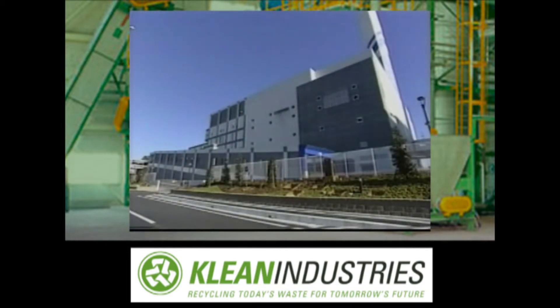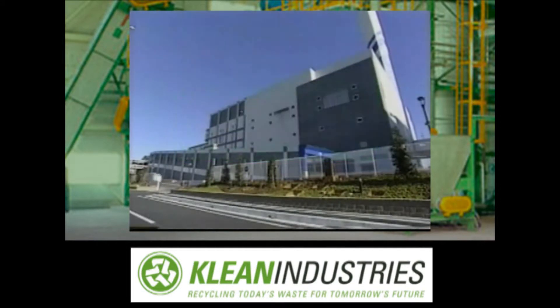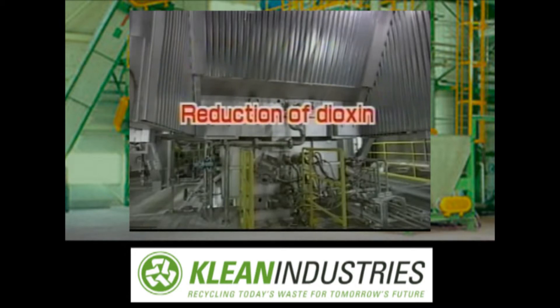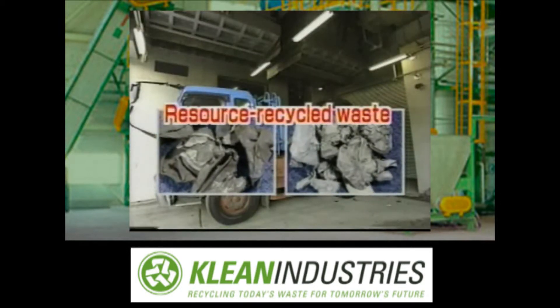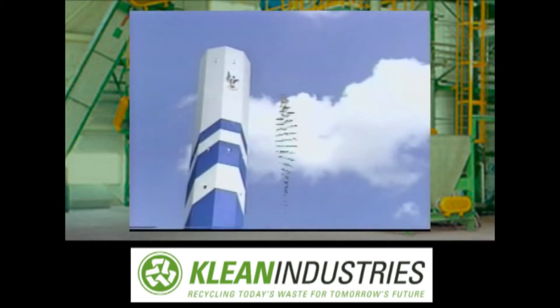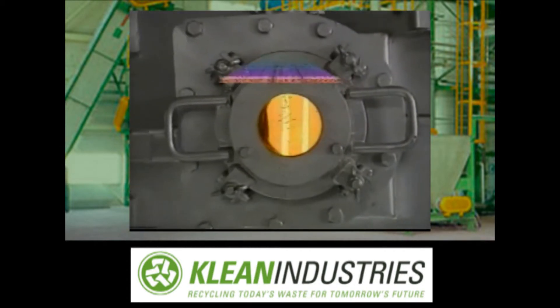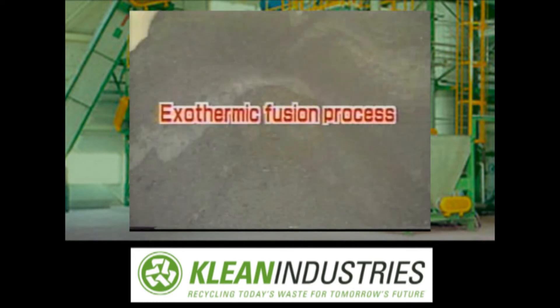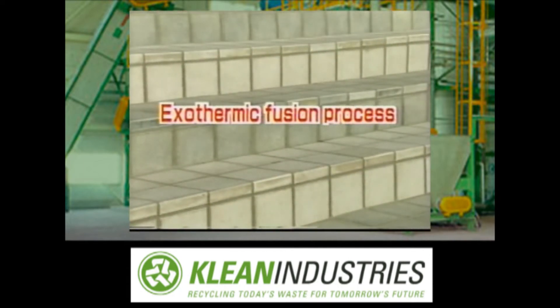Let's review the major merits and the latest technology of the Asahi Clean Center's gasification and ash melting facility. The high temperature treatment dramatically reduces dioxin. Ferrous and aluminum are recovered in a non-oxidized state suitable for reuse. By reducing the air ratio, the flue gas volume is reduced to minimize environmental loads. Fly ash is melted and becomes slag by the heat energy contained in the waste, and the recovered slag is used as a material for sidewalk blocks and other like products.